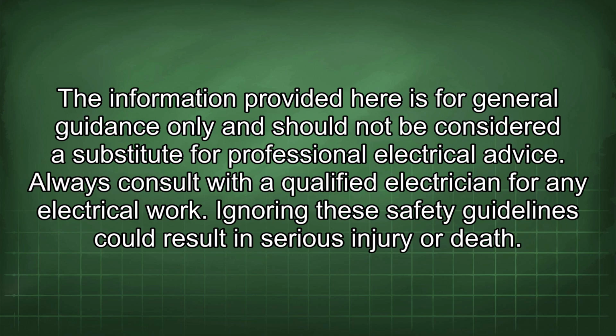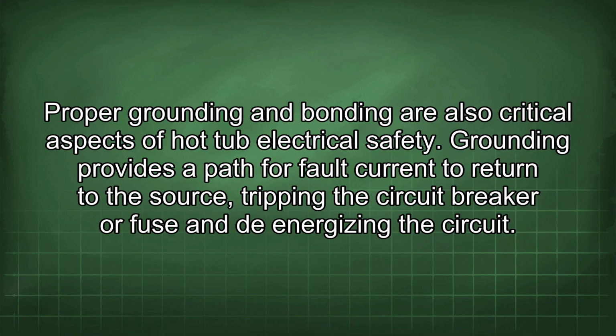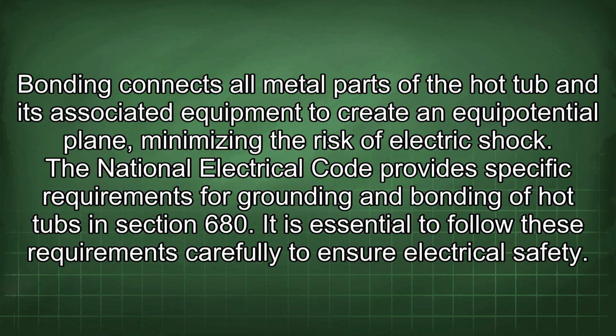Ignoring these safety guidelines could result in serious injury or death. Proper grounding and bonding are also critical aspects of hot tub electrical safety. Grounding provides a path for fault current to return to the source, tripping the circuit breaker or fuse and de-energizing the circuit. Bonding connects all metal parts of the hot tub and its associated equipment to create an equipotential plane, minimizing the risk of electric shock. The National Electrical Code provides specific requirements for grounding and bonding of hot tubs in Section 680. It is essential to follow these requirements carefully to ensure electrical safety.